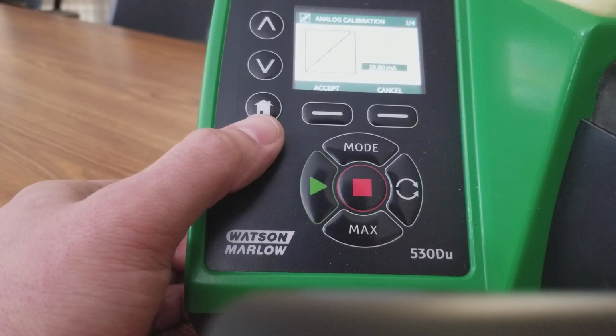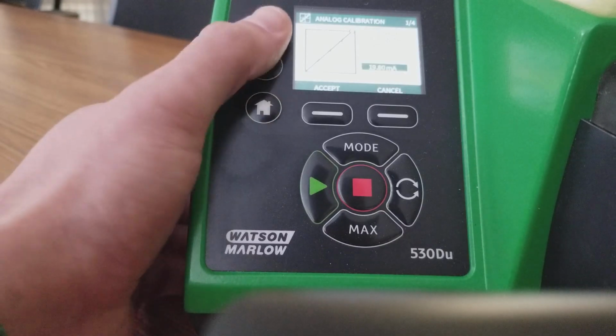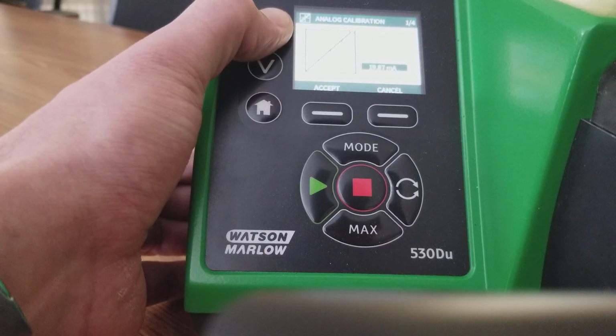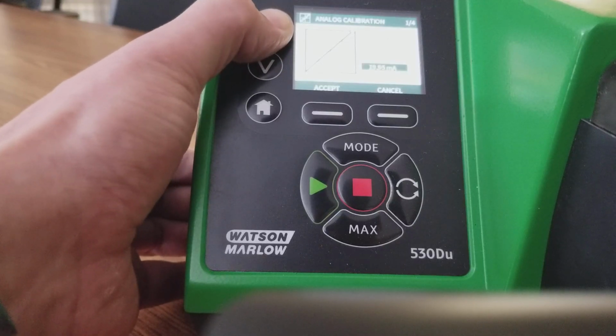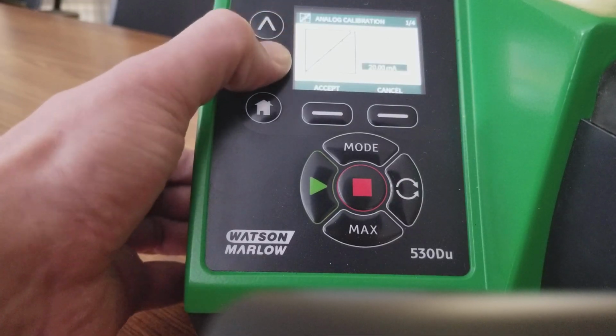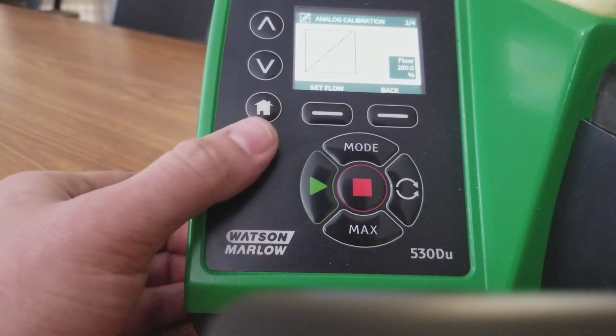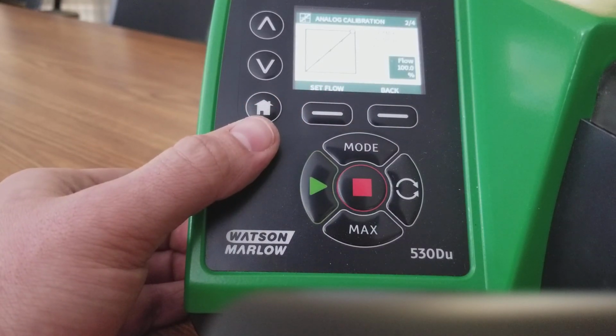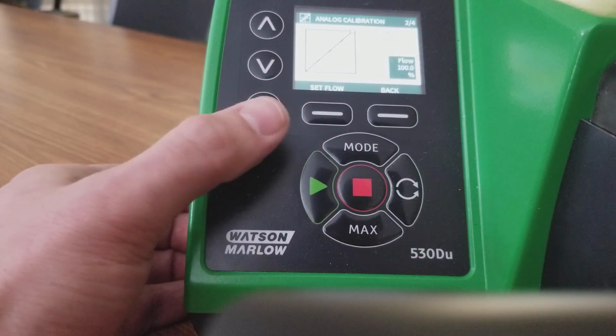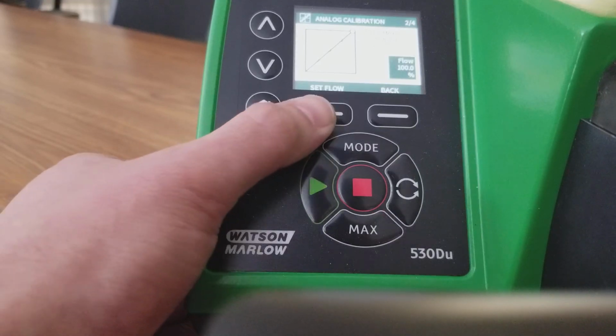Right now what you're seeing is they want the high value. Unfortunately, Watson Marlow has not corrected this problem, so 19.8 milliamps is what comes from factory. So we're going to want to bump this up to 20 milliamps just by hitting the up arrow key. At that time we'll select enter. I'll show you a shortcut to figure out the flow percentages, but for now we're going to leave it at 100%.